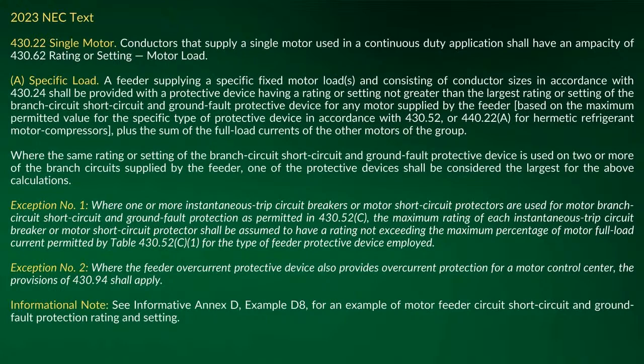In all the stuff that I do, every single thing is an individual branch circuit. Typically we don't have multiple motors on an individual branch circuit. It's not been uncommon, though. Let's say you have an intake and an exhaust, then yeah, they might want them on the same branch circuit, so that if one trips, they both trip. Or there are certain times where it's an engineering design application where it makes sense to put them both on the same branch circuit. Sure.